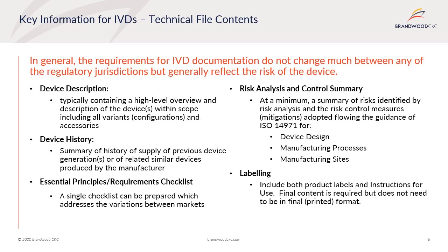So we've talked about the types of IVDs, we've talked about the classification of those different types, and we've talked about some standards that are appropriate to IVDs. But I think it's really important to understand what kind of information is required when it comes to regulatory activities with IVDs. So what we've tried to do here in the next few slides is outline the clinical or the technical file contents that would be expected for an IVD. Now again, technical file, design dossier, or DHF, I will use the terms synonymously, but depending on the jurisdiction, that's where those terms are going to be used.